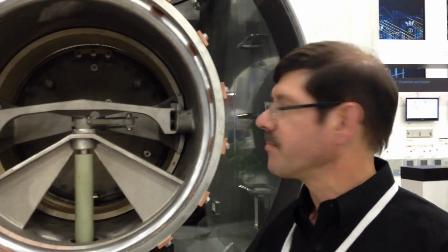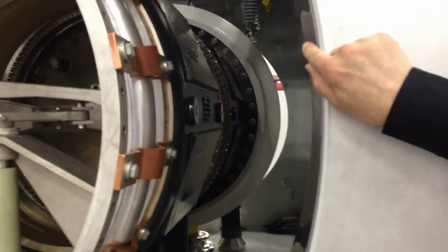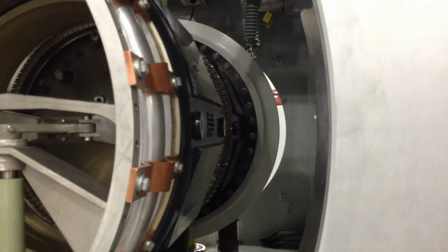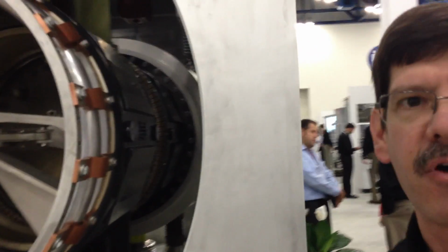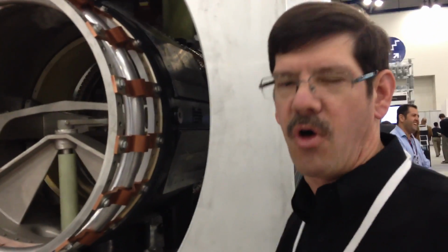Could you point out where does the actual switch occur here? Are we able to see where that is? In the back portion of the enclosure, that is a chamber filled with SF6 gas, and that is where the actual arc is made and broken in order to quench the arc, to interrupt and operate the breaker under load.